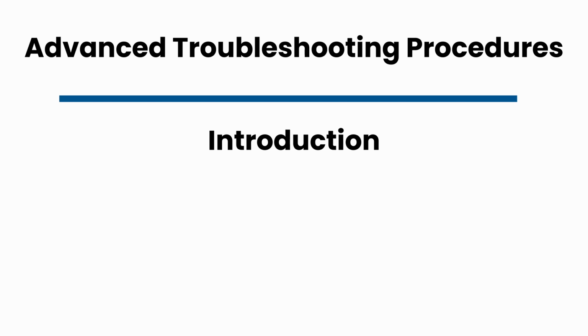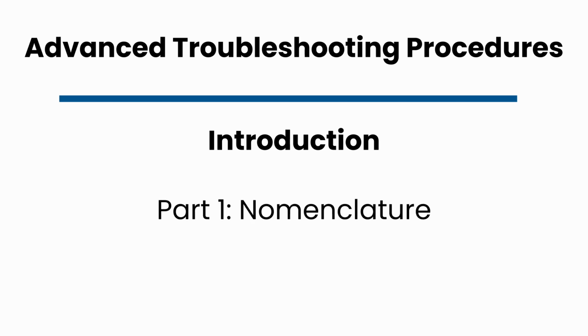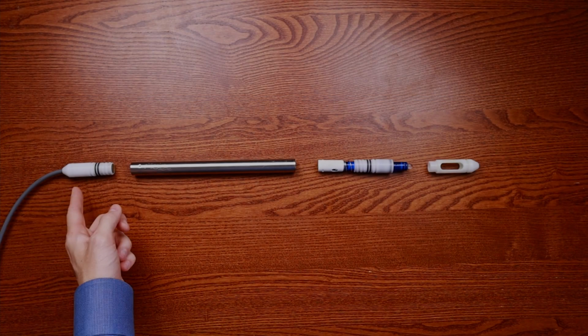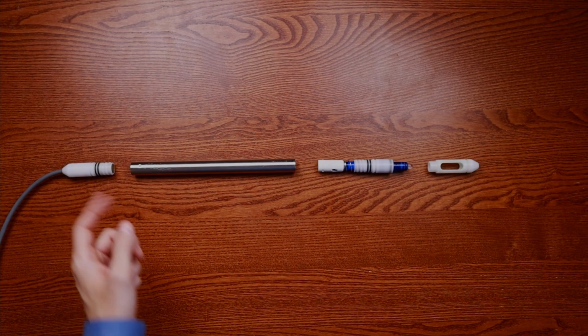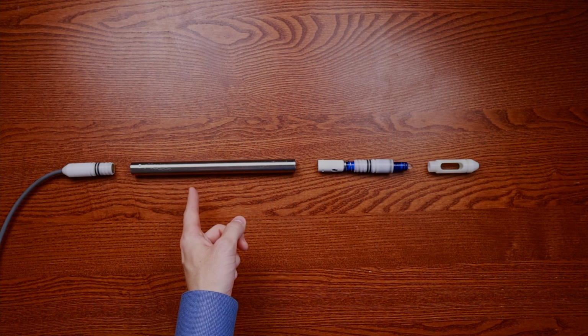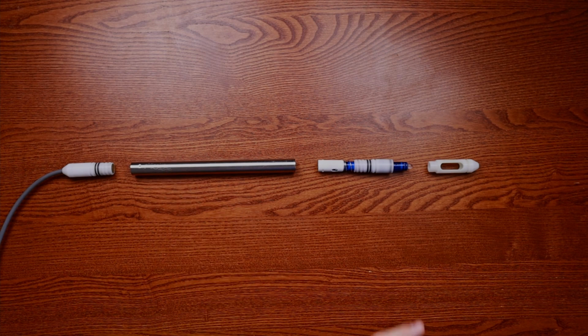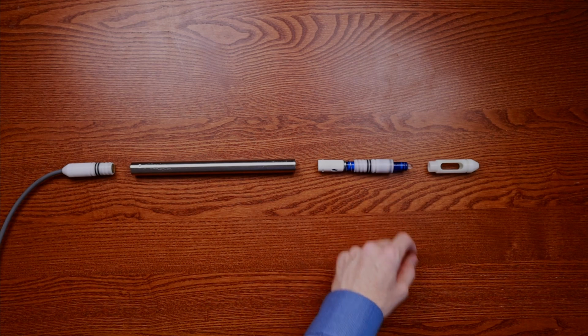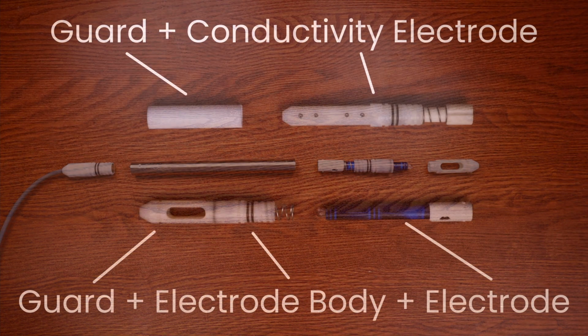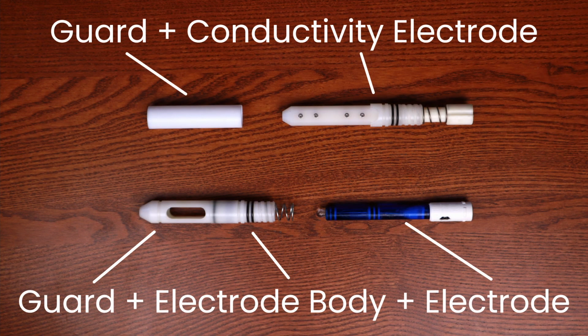But before going into the procedures, we must go over the nomenclature of STS series sensors so that instructions are clear. Here we have the cable connector, the housing with the circuit board inside, and the electrode inside the electrode body and protected by the electrode guard. Note that the design of conductivity sensors is slightly different, with the electrode and electrode body combined into a single part that cannot be separated.